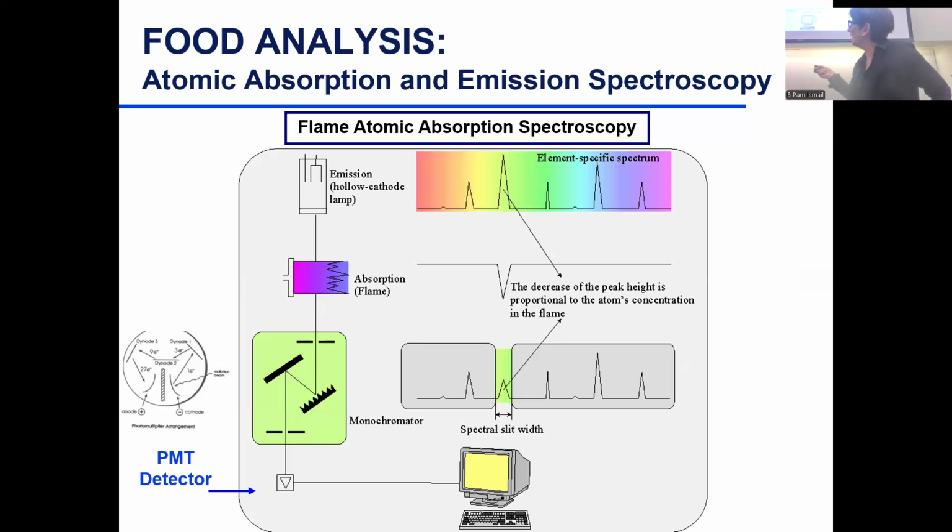So when the light hits the cathode, an electron jumps off and it goes to another, what do you call it here? Cathode, anode, something that will amplify the electrons, and it goes from one to the other, and the signal gets amplified. For example, one electron becomes 27 electrons, then you increase the sensitivity of the detector.